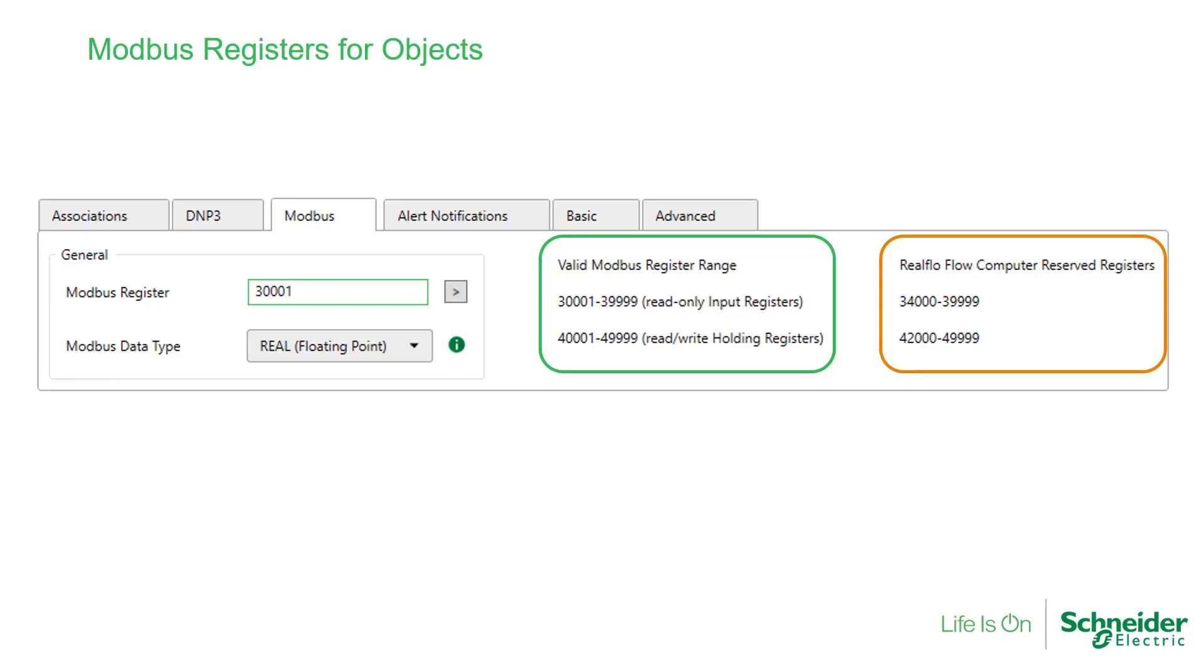So if you are porting a logic application from another SCADA pack flow computer to the SCADA pack X70, and it includes objects assigned to Modbus registers within this range reserved for Realflo, these objects will need to be changed to free registers outside the reserved range.